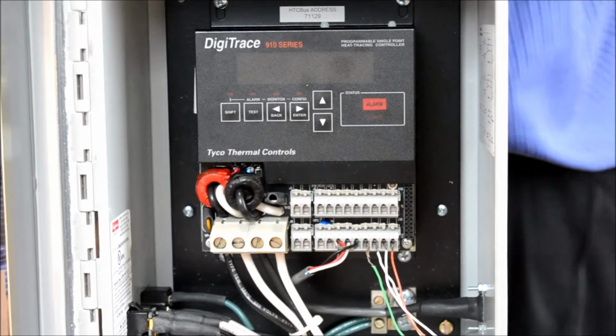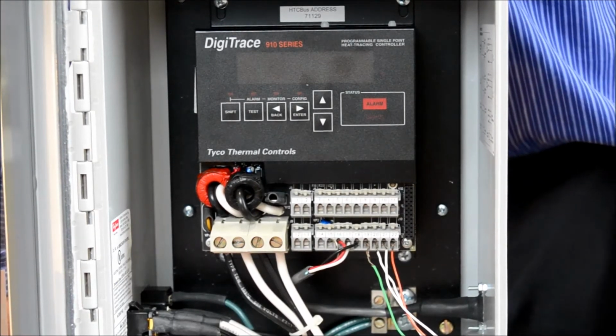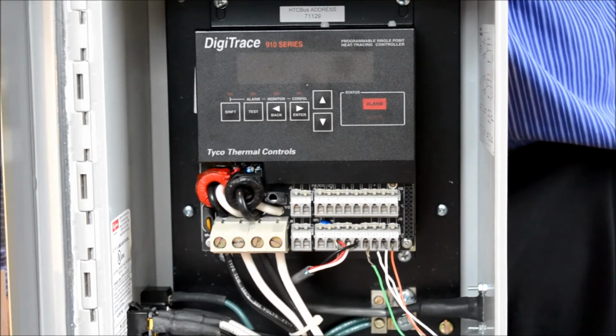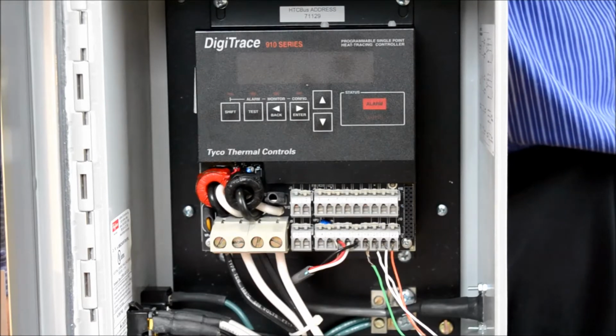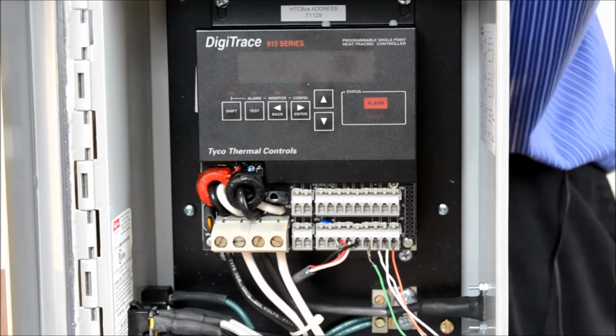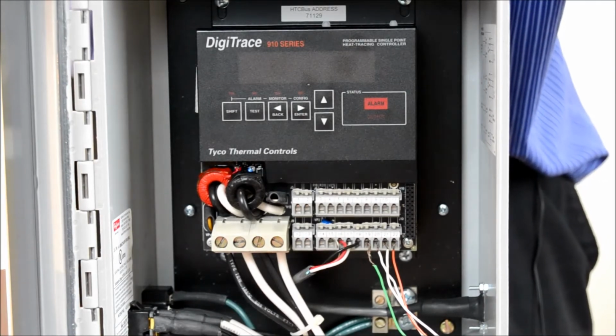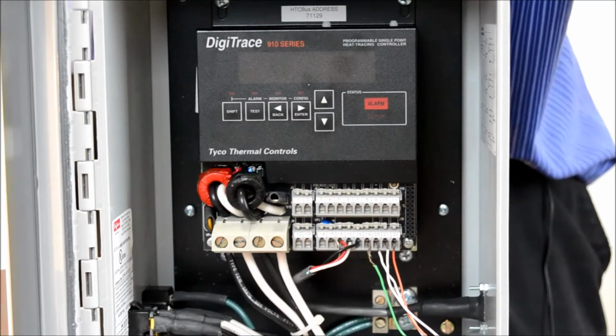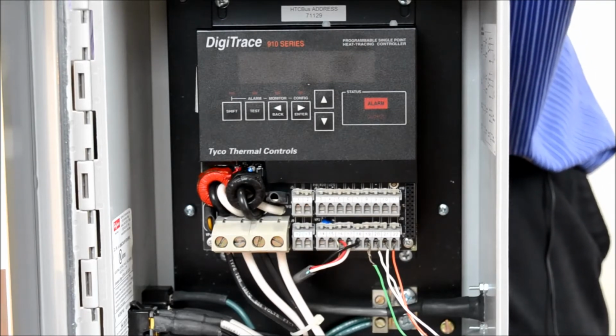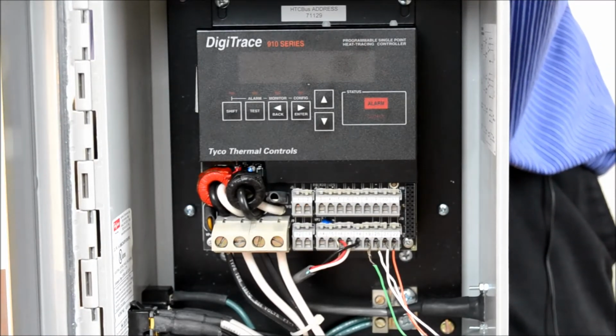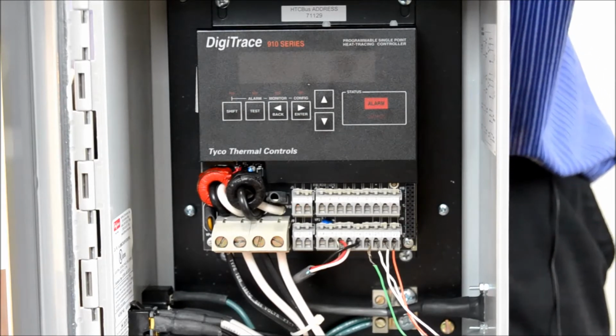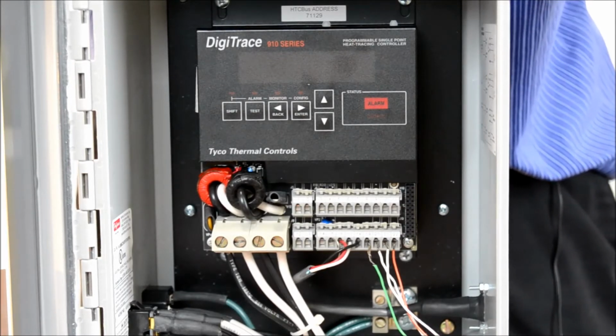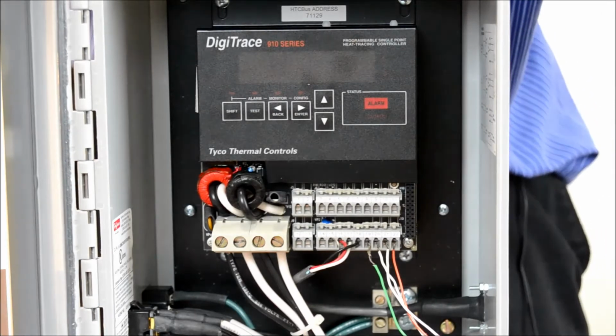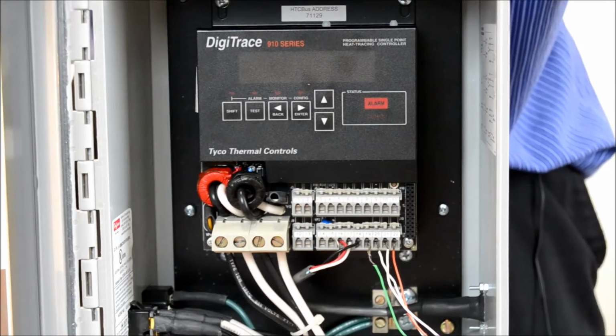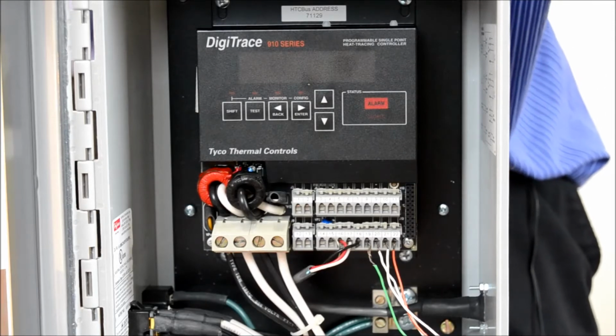And also another feature, the last one I'll talk about right now, is it has a proportional or deadband function on it. What that means is the deadband function is, say for instance this is a set point of 40 degrees. Well, if you have a 5-degree deadband, it won't shut off for 5 degrees above and below. So 35 or 45 degrees. So that's important. But if you want a more accurate reading, we have a proportional control.